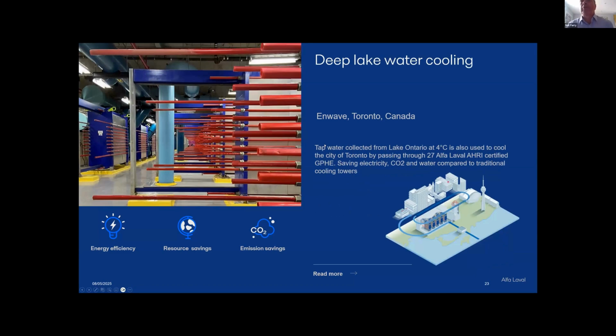This project I was at very recently, this is quite interesting. This is in Toronto. It's called the Deep Lake Water Cooling System, and the majority of downtown Toronto is cooled via free cooling from Lake Ontario. And you find throughout the year the variation in the temperature of the lake water is hardly anything. It alters by 1 to 2 degrees between summer and winter, so it's always really cool. So it allows them to provide cooling through various different substations that we have in the plant rooms and then in the individual buildings, and it provides cooling to downtown Toronto, as I mentioned.